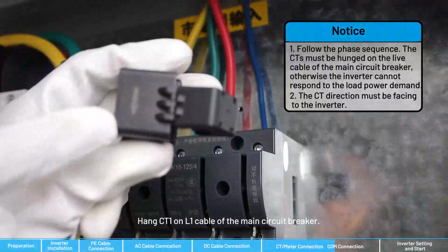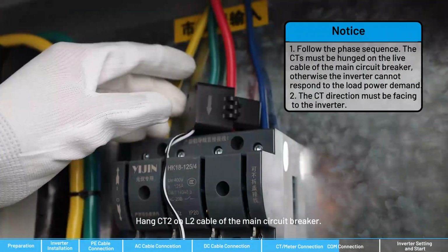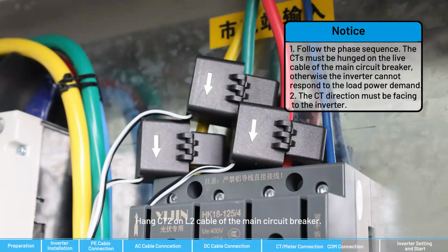Hang CT1 on the L1 cable of the main circuit breaker. Hang CT2 on the L2 cable of the main circuit breaker. Hang CT3 on the L3 cable of the main circuit breaker.